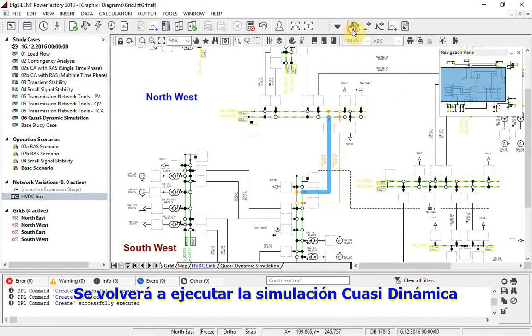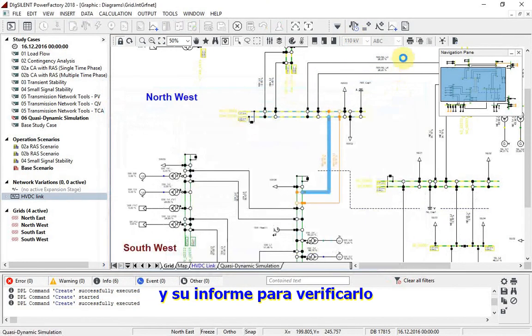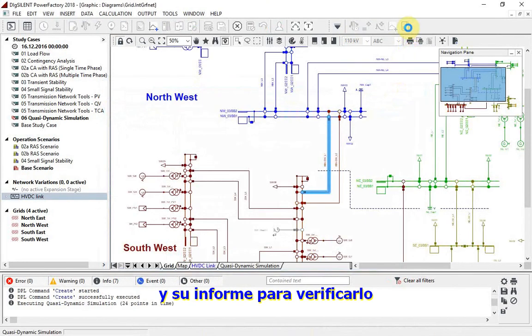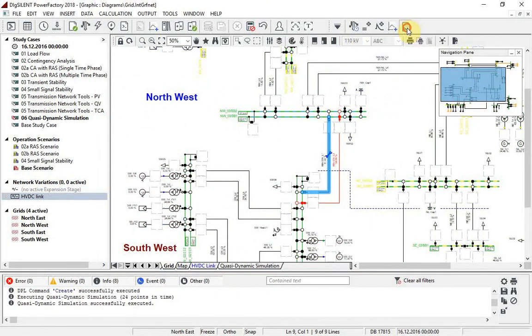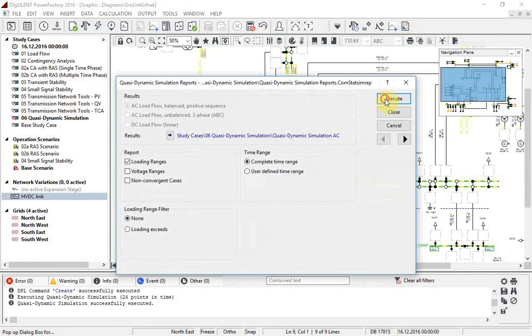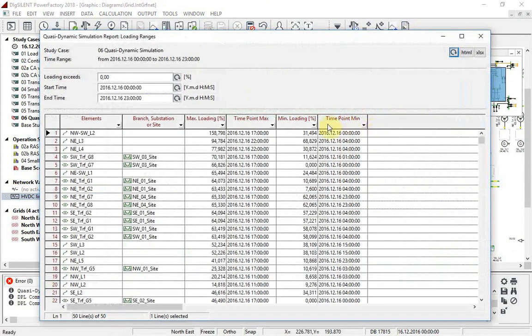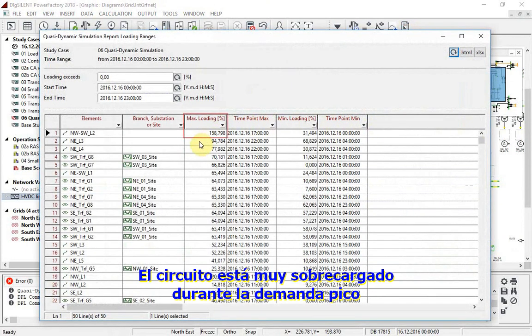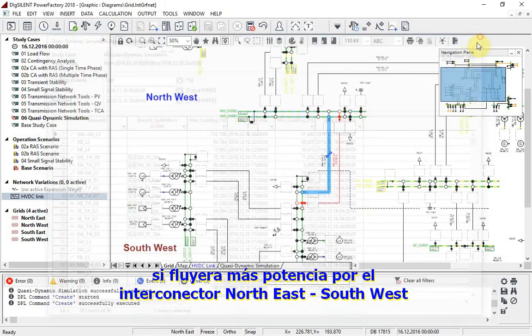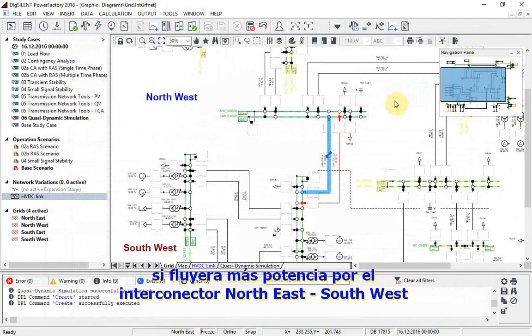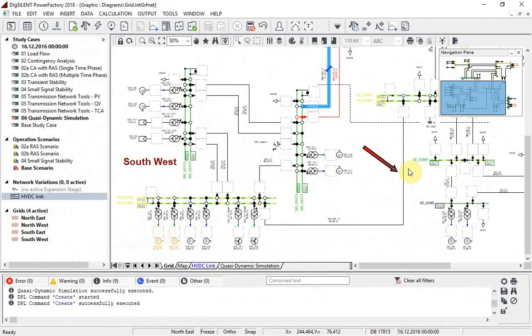The quasi-dynamic simulation and report are now re-run to check this. The circuit is now heavily overloaded at the time of peak demand. To manage this loading, it would be better if more power would flow through the north-east-south-west interconnector.